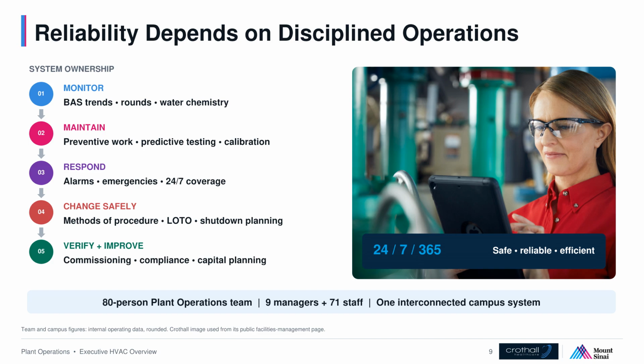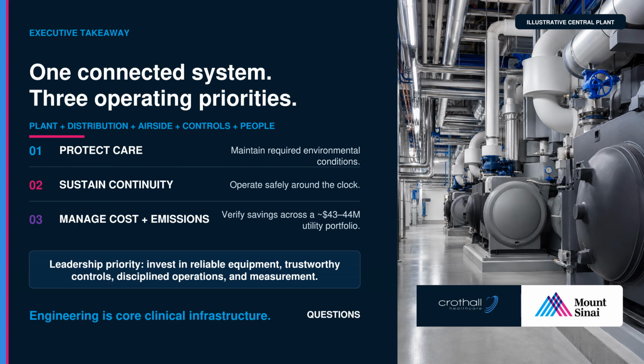Before a shutdown, ask, what spaces depend on this asset? What redundancy is real today? Who must know? And how will restoration be proven? After the work, do not stop at the equipment started. Confirm the intended flow, pressure, temperature, humidity, airflow, alarms, safeties, and room condition. That discipline is what turns equipment and controls into safe, reliable service 24 hours a day, 7 days a week, 365 days a year. The whole presentation reduces to one connected system and 3 priorities.